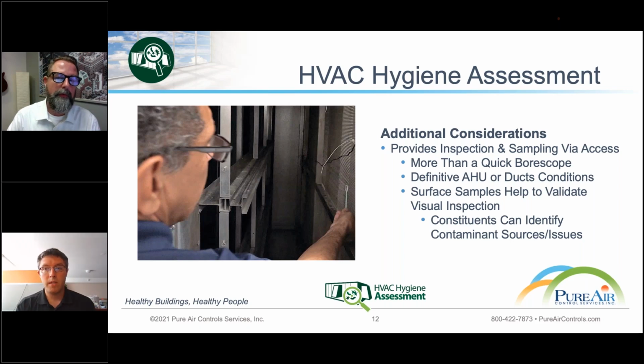So it's something to take very seriously when you see biofilm, not only from the human health standpoint, because we know that it could eventually aerosolize, especially with drying, wetting, or just continuing to grow, but also because it's indicative that we're going to start to see some significant corrosion over time of our drain pan, which is what's keeping water from leaking out of the unit into other areas. So it's kind of twofold when you see biofilm, because there's been a lot of standing water for some time.